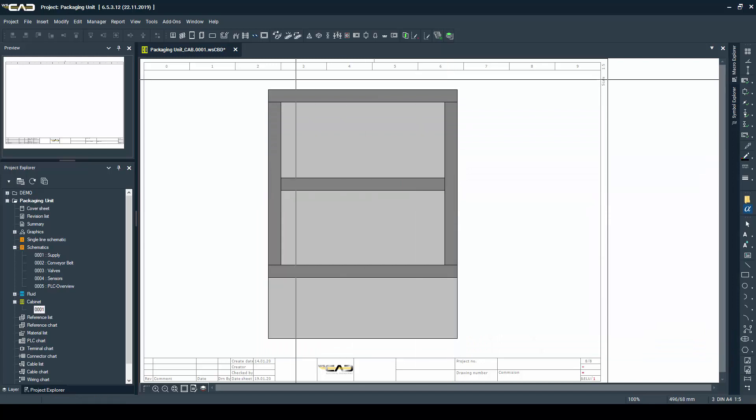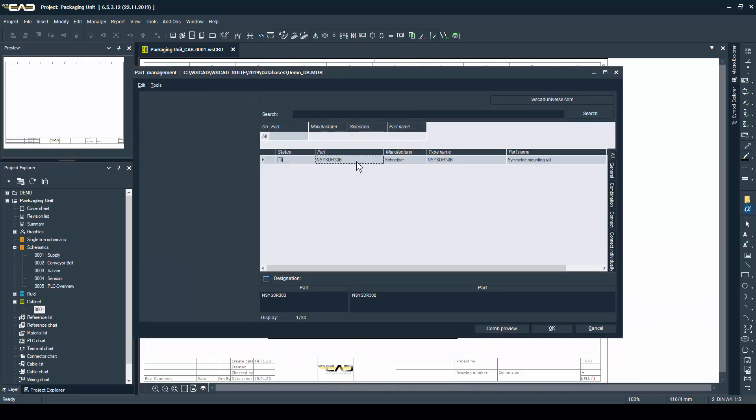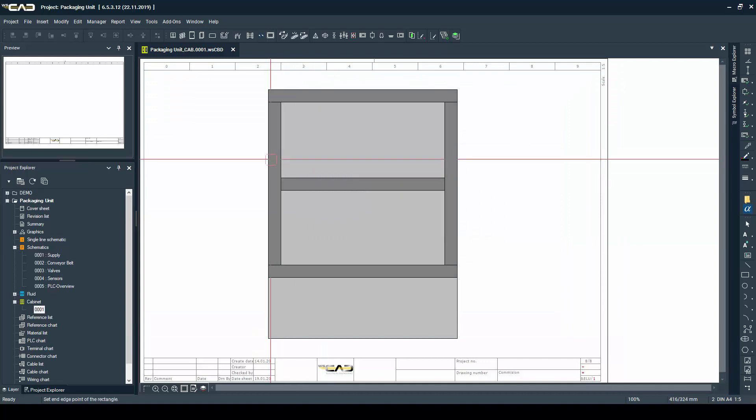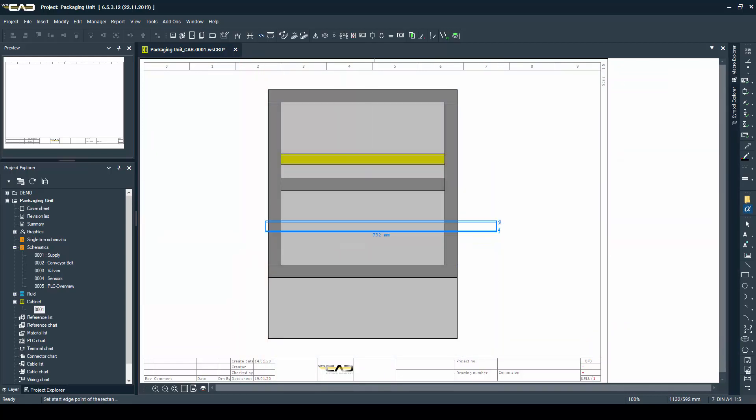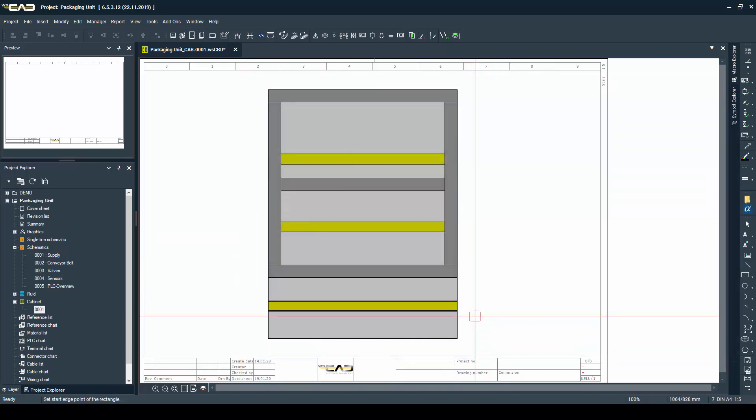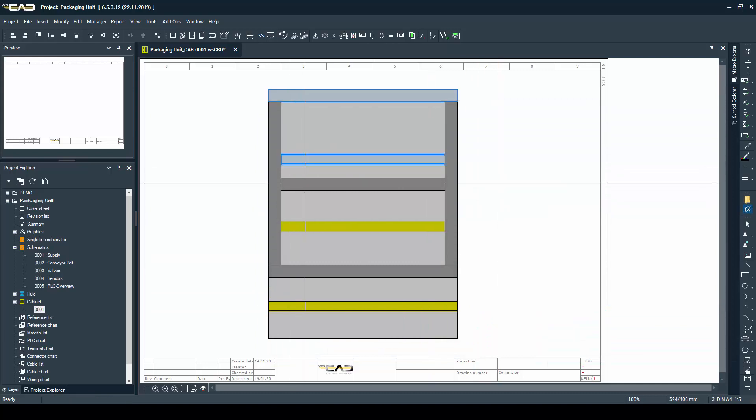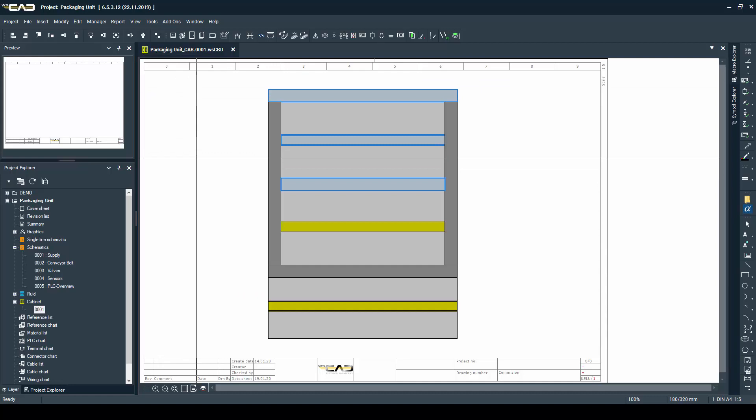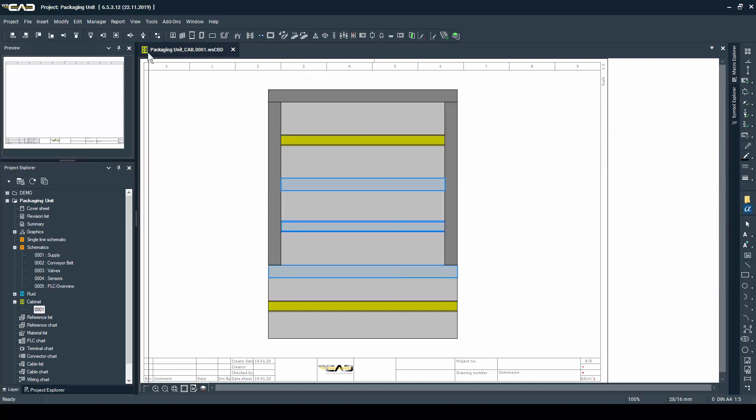Then you will need a din rail. And like with the cable tray, you don't need to work with high accuracy because even if you made a mistake, you can always go back to the alignment objects toolbar. This will allow you to, for example, snap the din rail in the middle point of the two cable trays where it's placed.